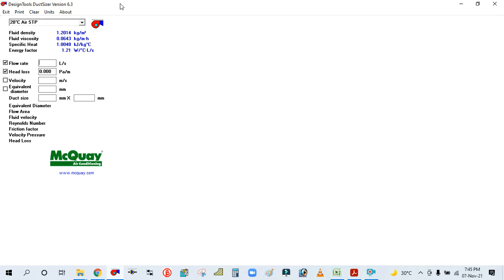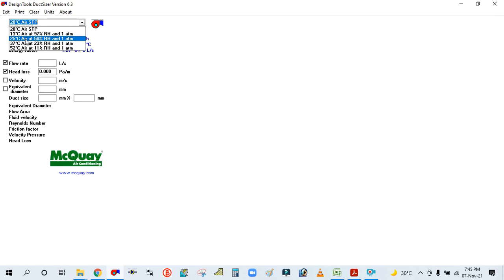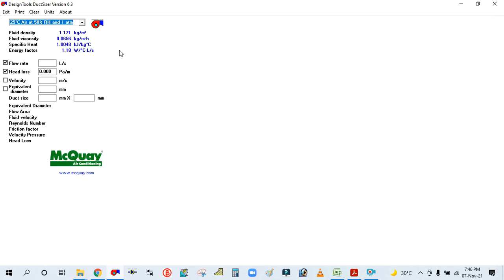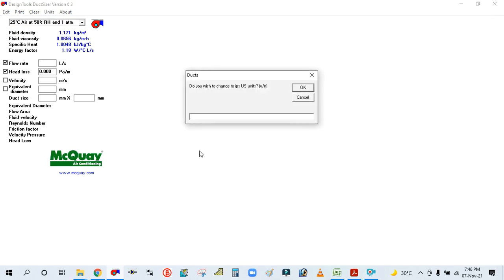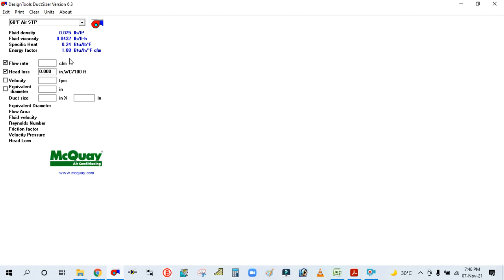Before starting duct design with McQuay, we need to do some settings. You can see here there is a dropdown button — click here and set the condition. Our condition is 25°C air temperature, 50% RH, and 1 atmospheric pressure — this is the indoor room comfort condition. To match this in imperial, select 75°F at 50% relative humidity and 1 atmospheric pressure.